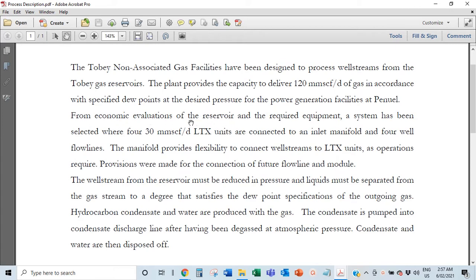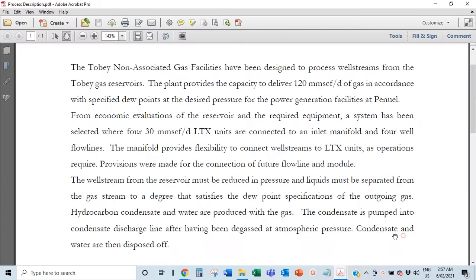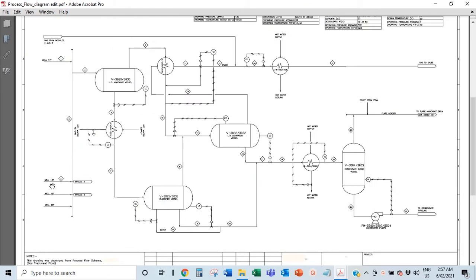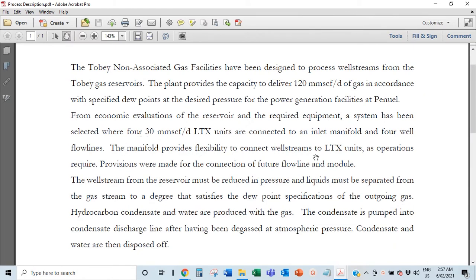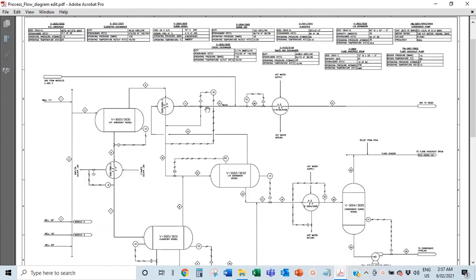So there are many things in place just to make sure the stream is constant at the right temperature and pressure for those turbines. From economic evaluations, four trains of 30 million SCFD were selected, connected to an inlet manifold. The manifold is just a collection of pipes — all four trains connect to this one pipe. Four well flow lines feed in, and the manifold provides flexibility to connect well streams to LTX units as operations require.